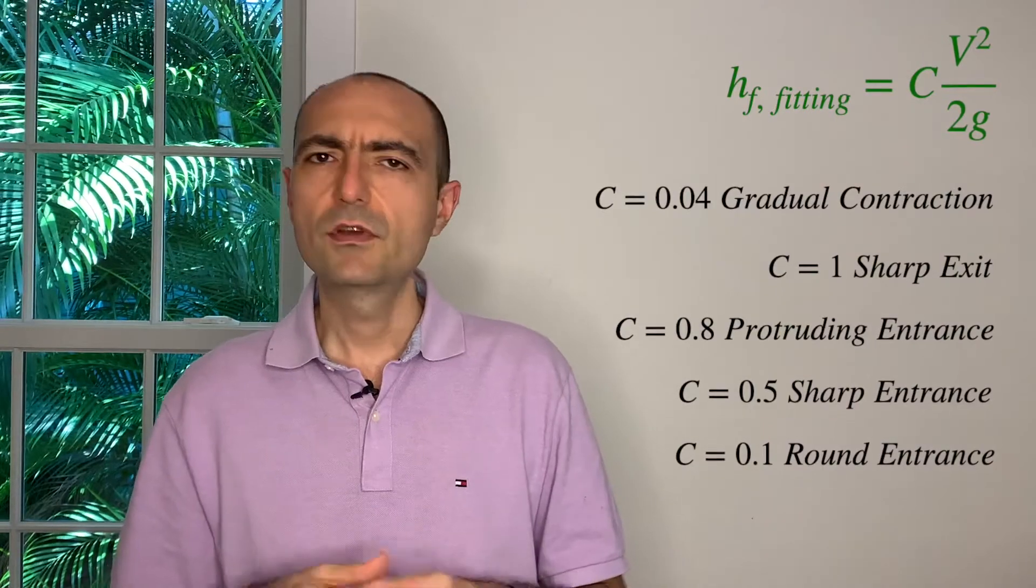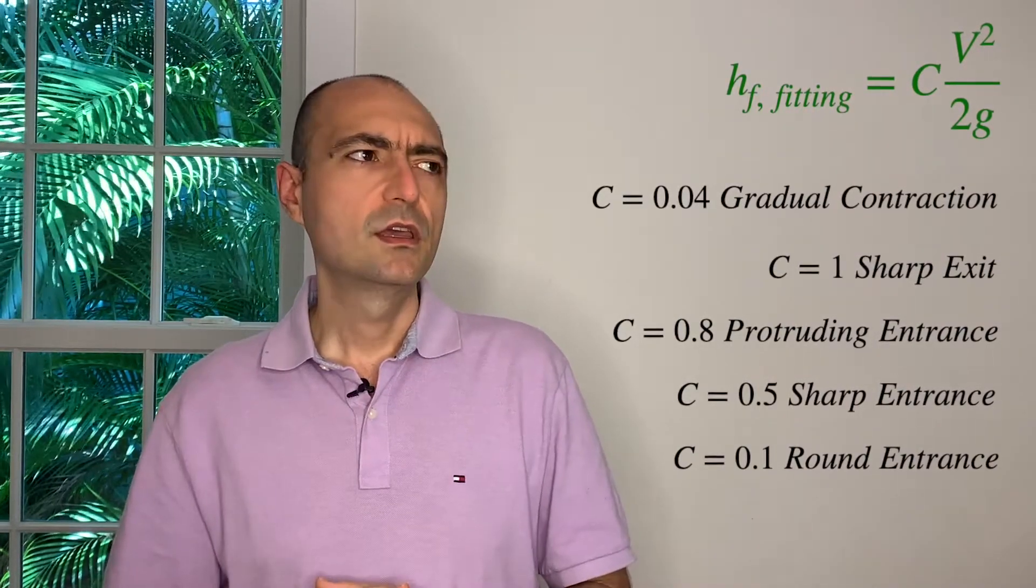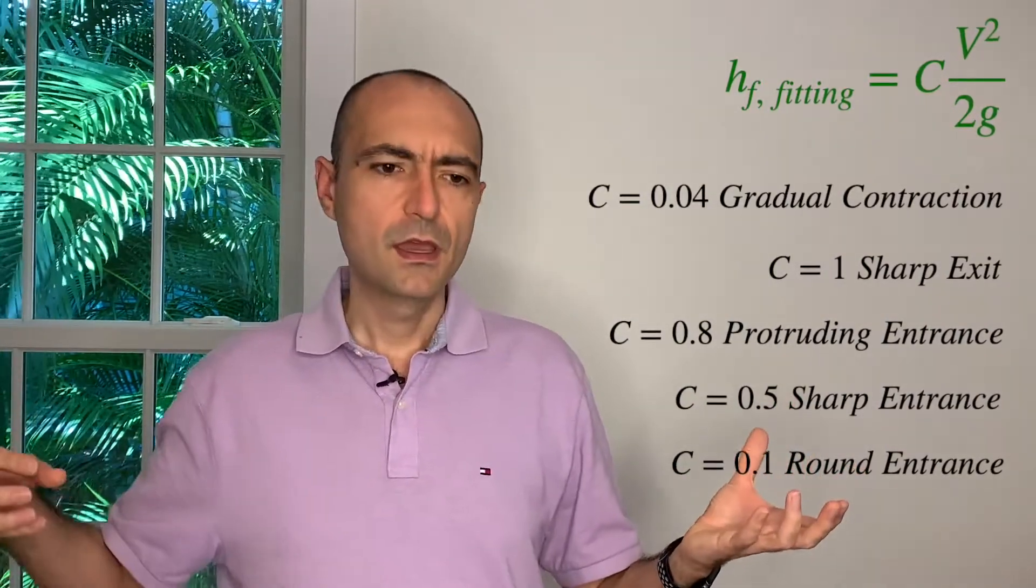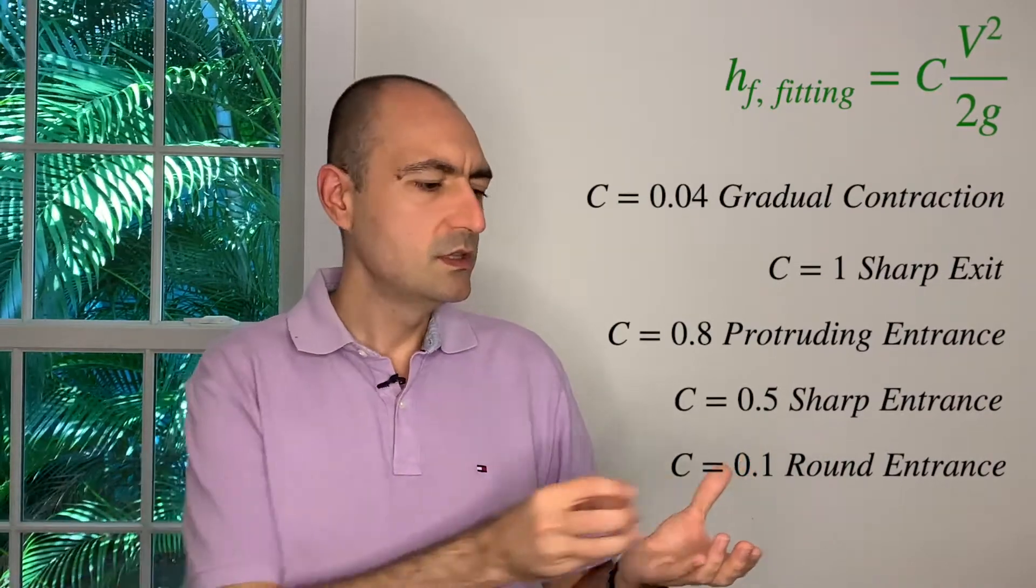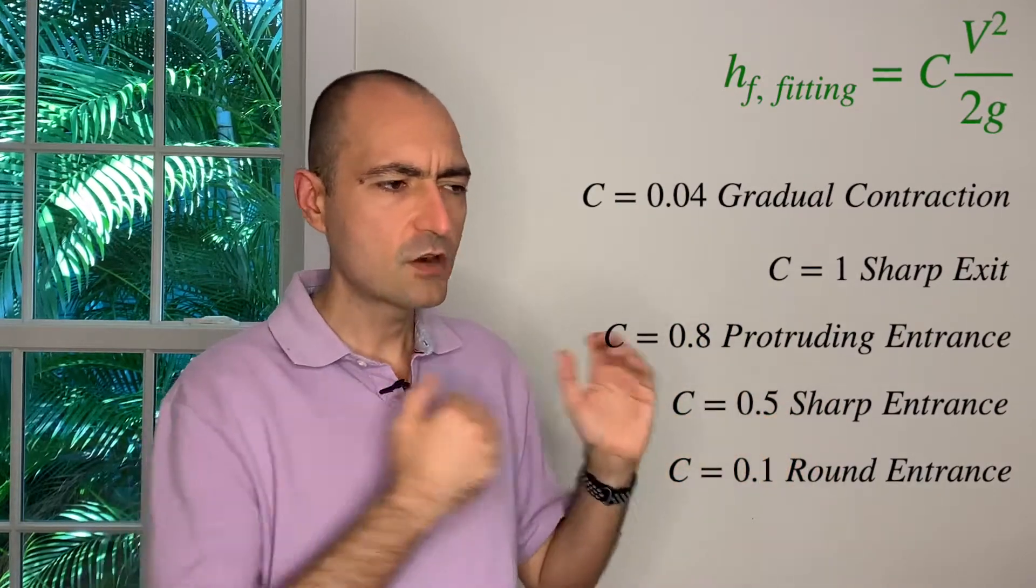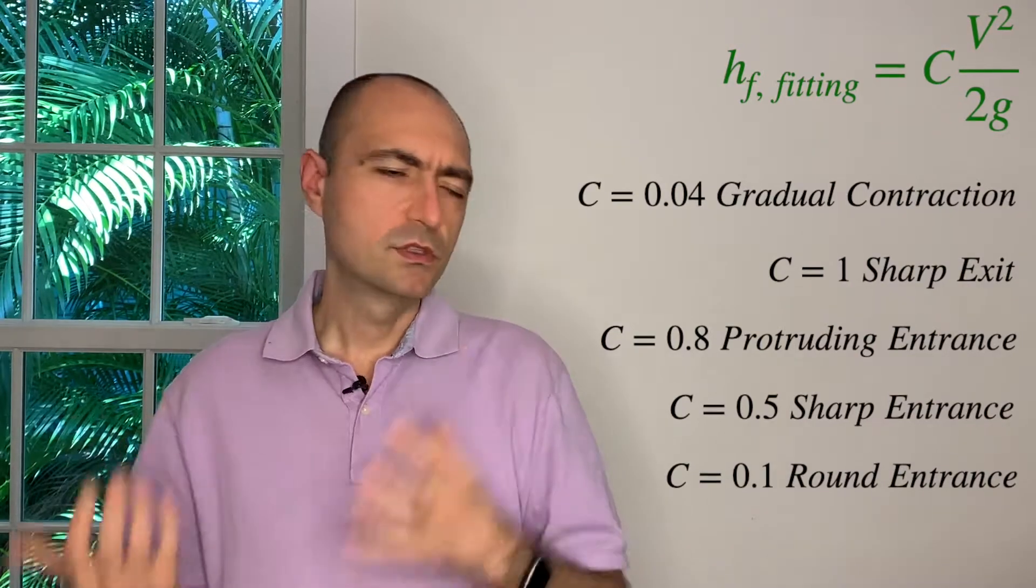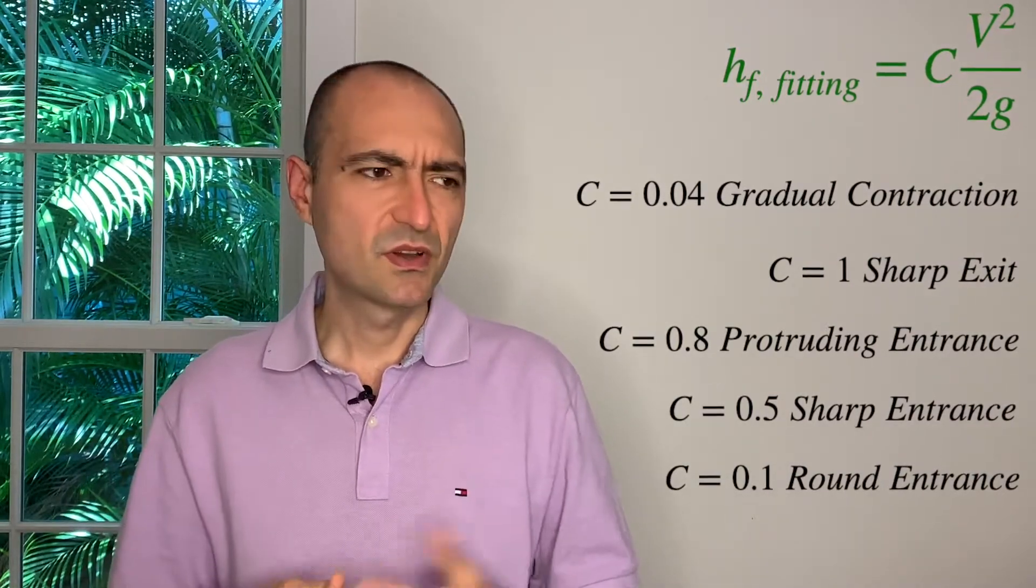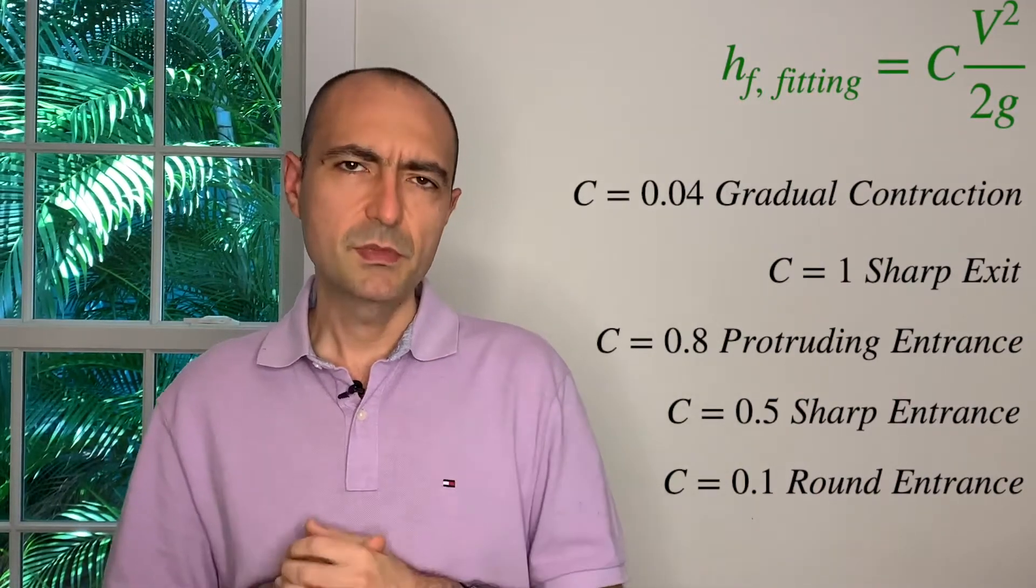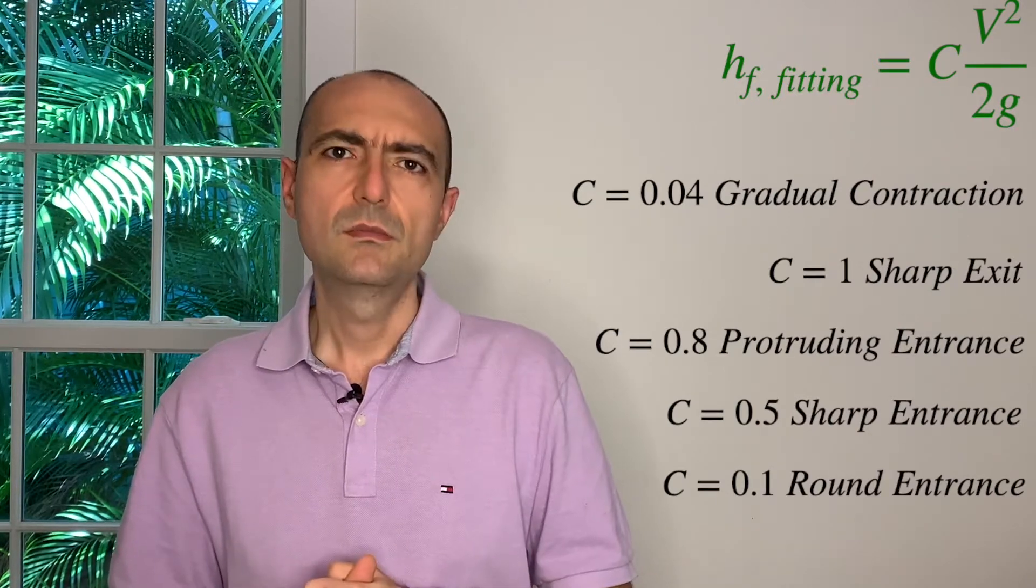And just very briefly, if I have a gradual contraction, it's going to be 0.04. If I have an inlet, let's say there's a tank and there's a pipe, and if this pipe is protruding into the tank, that will be 0.8. If I have a sharp entrance, it will be 0.5. If I have rounded, it equals 0.1, but it kind of changes as a function of the radius of curvature. And for each exit that I have, it's going to be 1. This information will be supplied to you, and it's given to you on page 183 of the reference manual.